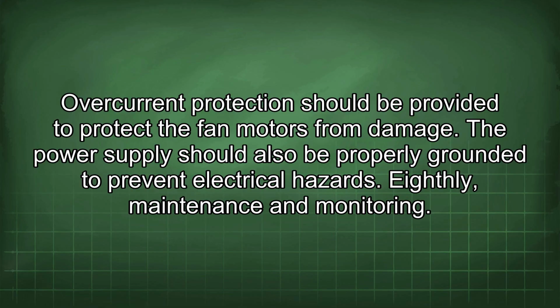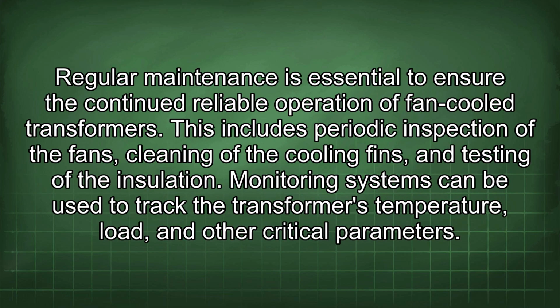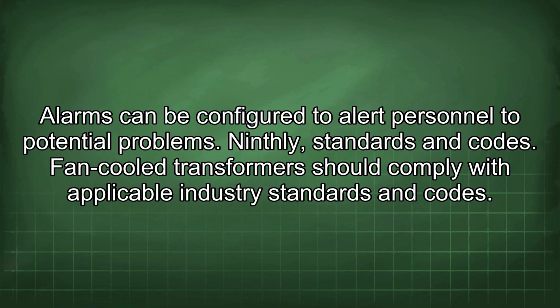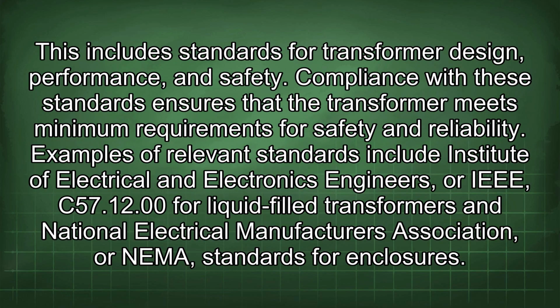Eighthly, maintenance and monitoring. Regular maintenance is essential to ensure the continued reliable operation of fan-cooled transformers. This includes periodic inspection of the fans, cleaning of the cooling fins, and testing of the insulation. Monitoring systems can be used to track the transformer's temperature, load, and other critical parameters. Alarms can be configured to alert personnel to potential problems. Ninthly, standards and codes. Fan-cooled transformers should comply with applicable industry standards and codes. This includes standards for transformer design, performance, and safety. Compliance with these standards ensures that the transformer meets minimum requirements for safety and reliability.